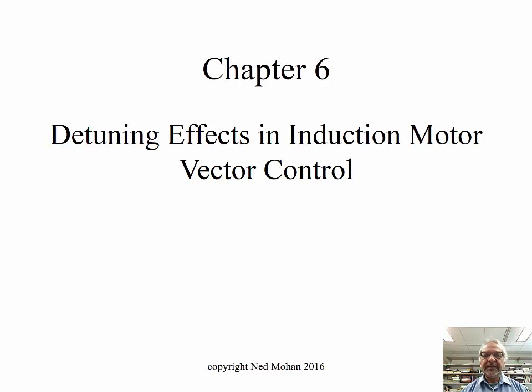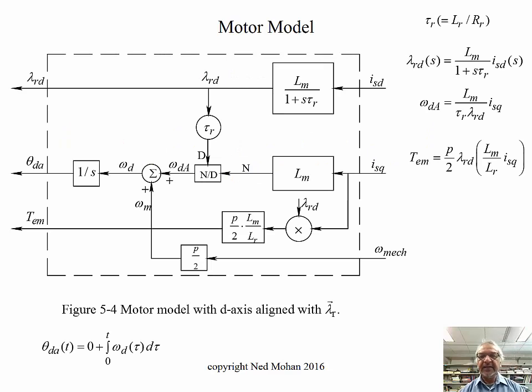So in this chapter, we will see what happens if our estimate of motor parameters are not absolutely correct. That was a question I had when I started to learn about this material, and that's what I'd like to clarify in this chapter. Borrowing this slide from chapter 5, we saw how we estimate, for example, the position of the rotor flux linkage with which we would like to align d-axis in order to do vector control.